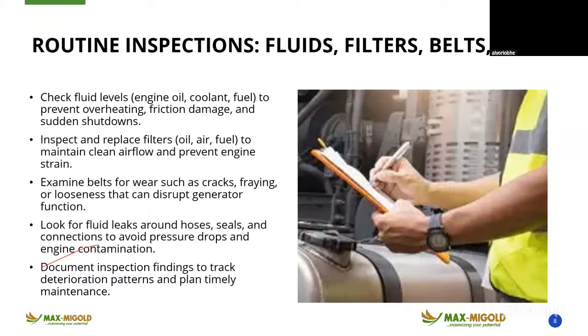Belt also: examine belts for wear such as cracks, fraying, and loosening that can disrupt generator function. Look for fluid leaks around hoses, seals, and connections to avoid pressure drop and engine contamination. Document inspection findings to track deterioration patterns and plan timely maintenance. So when you notice anything, ensure you put it in writing, in your book, your document, so that you have a history of the generator.